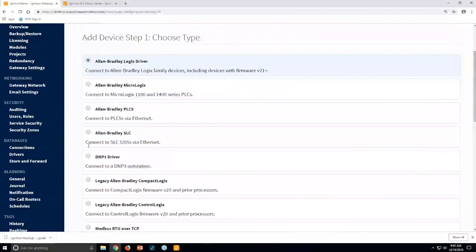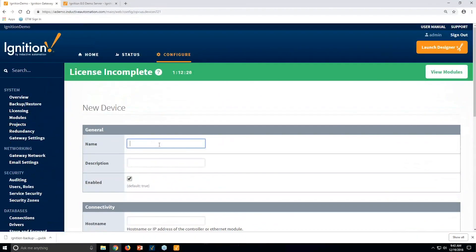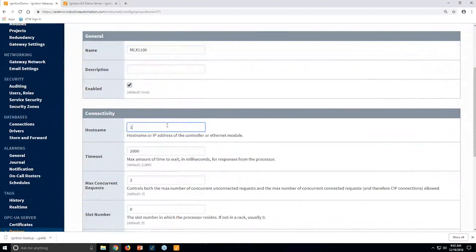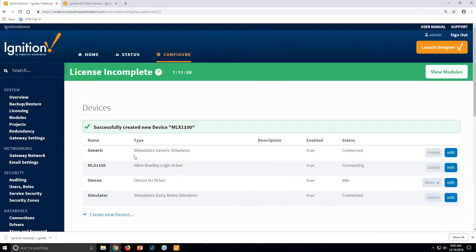For example, if I had an Allen-Bradley Logix device — which covers most of the new Allen-Bradley drivers created today — I can come in and connect up to a MicroLogix 1100. It would probably be named based on the area you're in, but I'll use 10.20.7.77, which is inside our network. Once connected, we can see it's connected and idle right there.